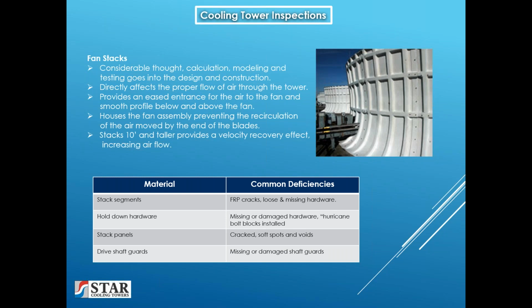The stacks should be inspected for cracks, loose or missing hardware. The hold down hardware, particularly the hurricane bolting blocks, should be examined to make sure that they're in good order. Stack panels, looking for cracked or soft spots and voids, and making sure that the drive shaft guards are intact and have no damage.